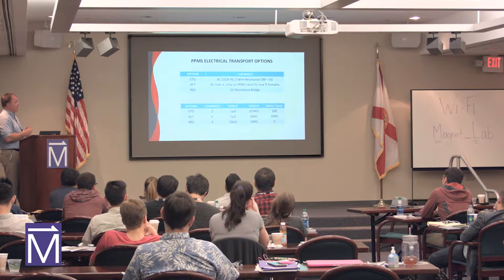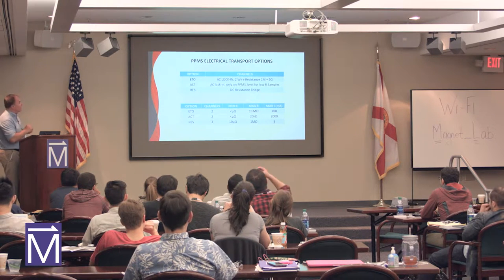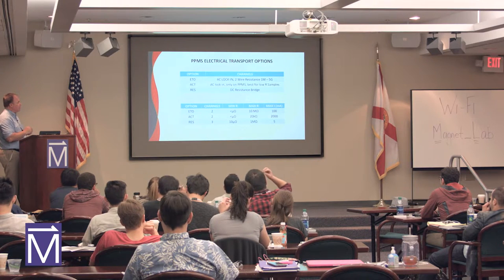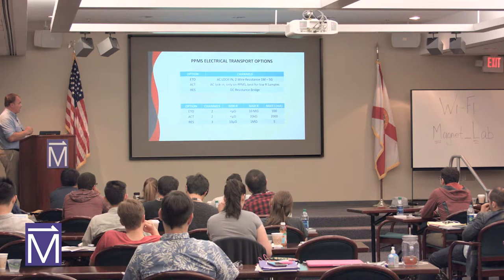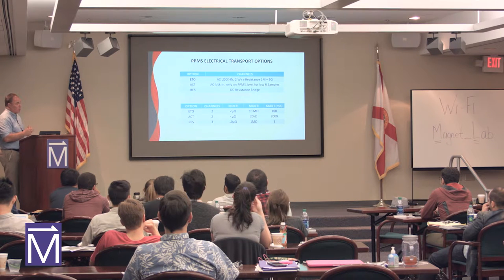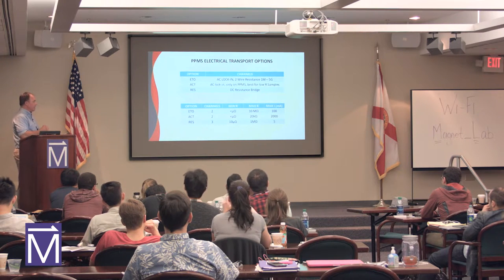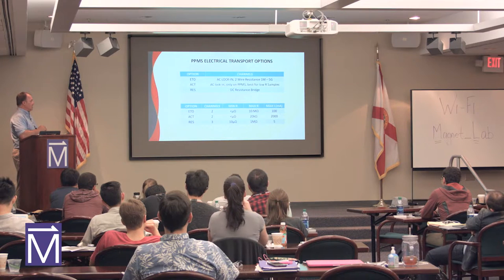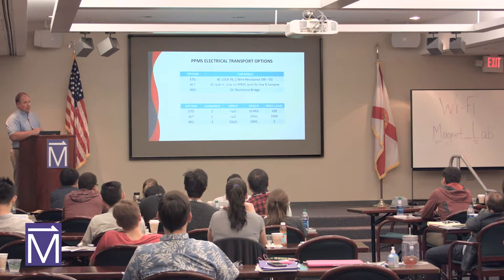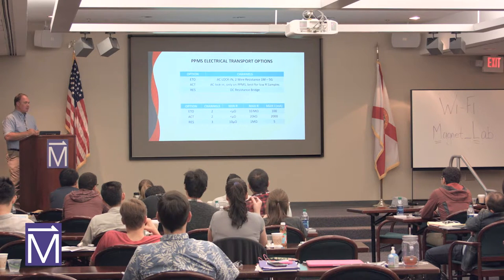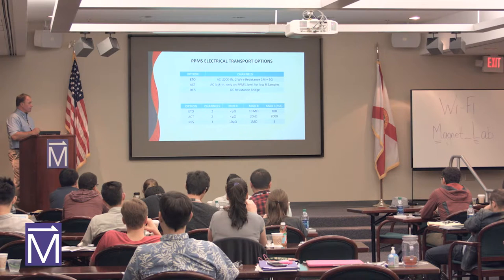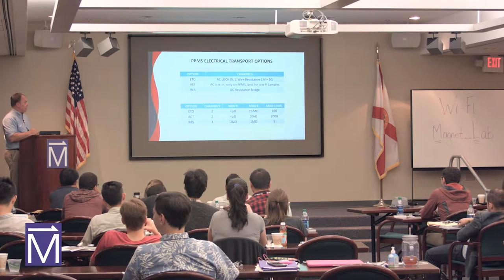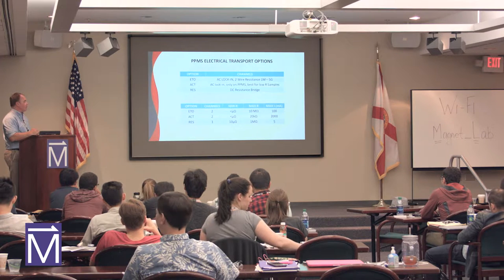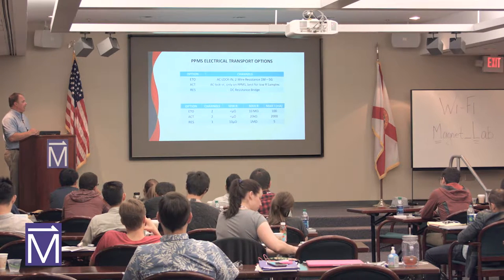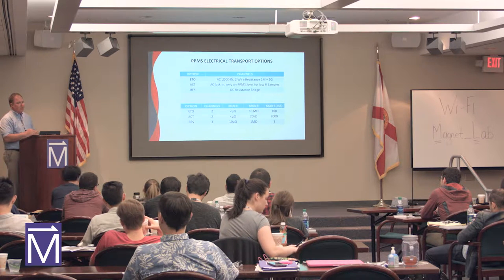Here's a little summary of what I just said. The ETO is an AC lock-in technique, two-wire resistance, and the resistance range should be 1 megaohm to 5 gigaohm. ACT is a lock-in based technique, only on the PPMS versions, for low resistance samples and critical current type measurements. The resistivity is a DC bridge. And then we talk about the number of channels and the maximum current. With the ACT option, the AC transport, you can put 2 amp output through. Resistivity is 5 milliamps, and ETO is 100 milliamp current through your sample.